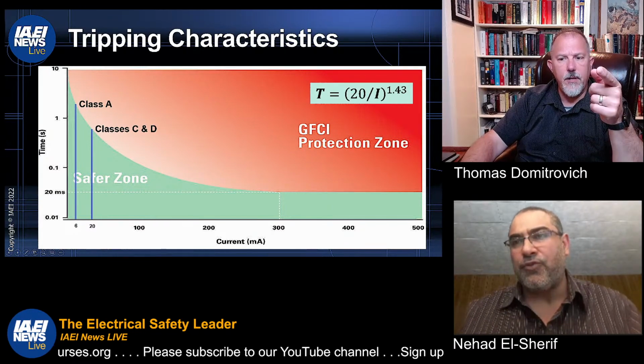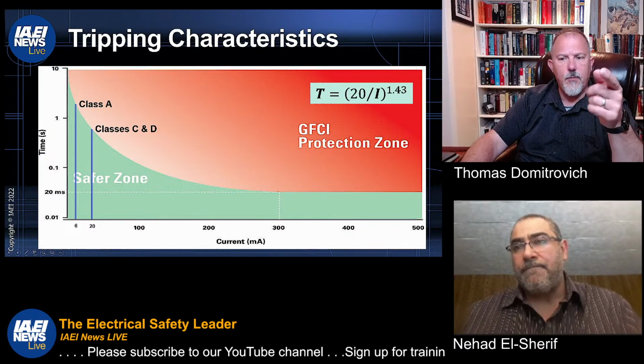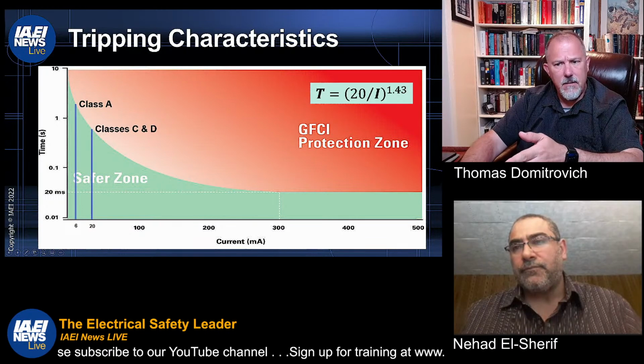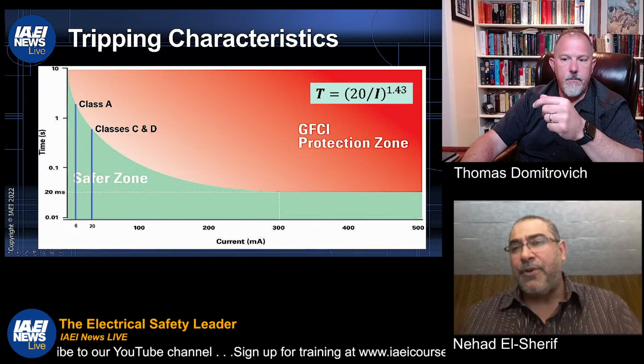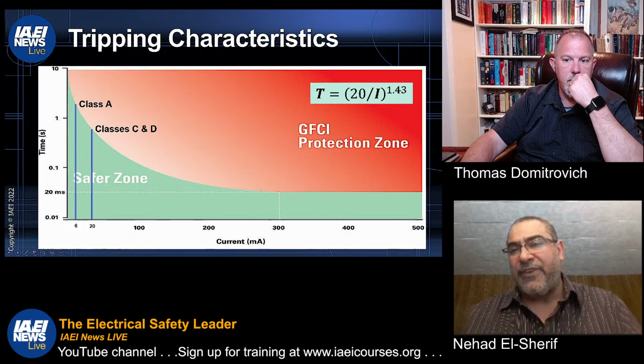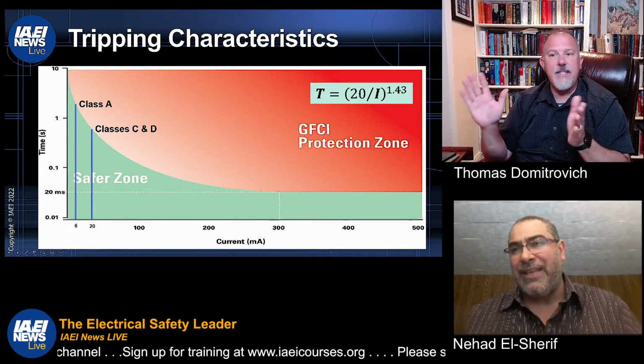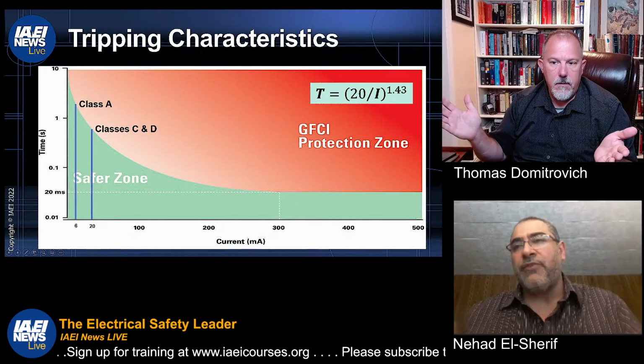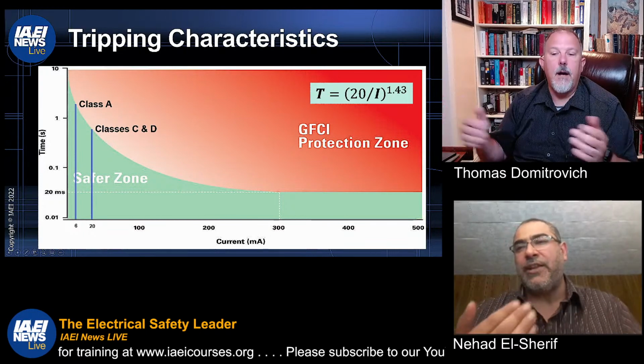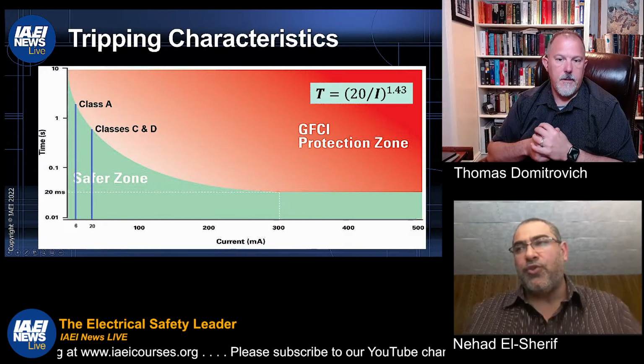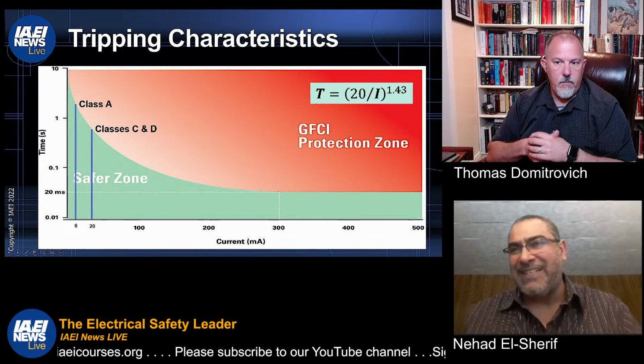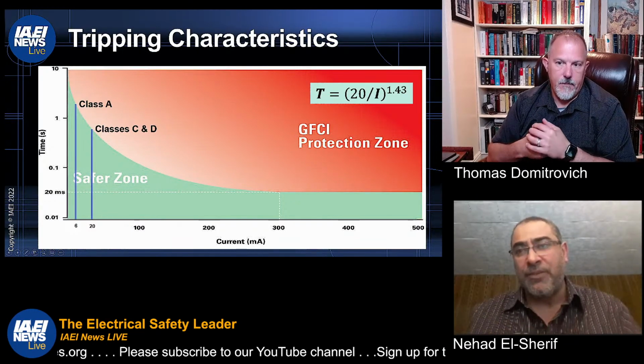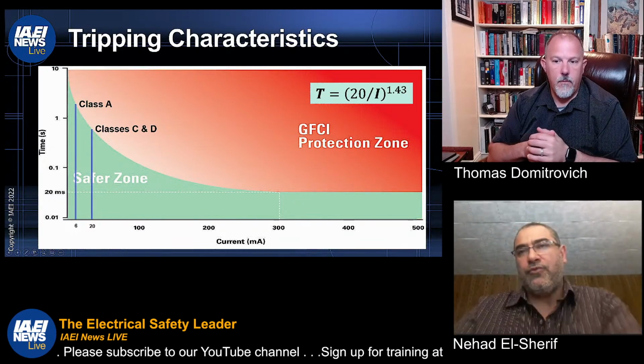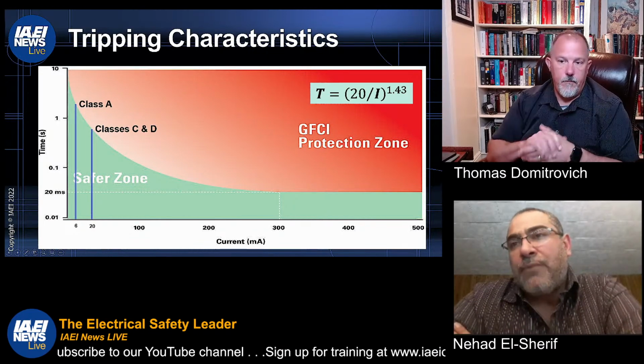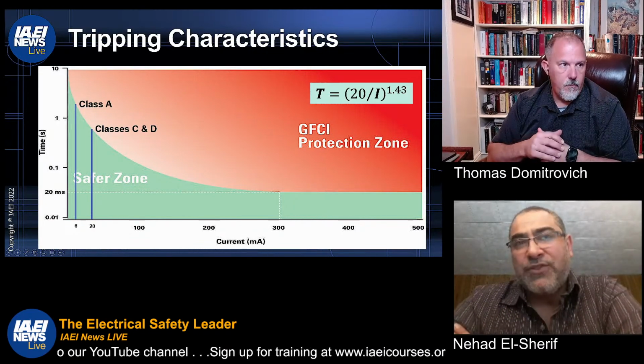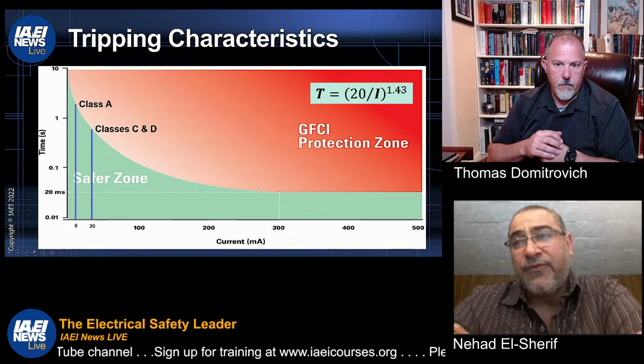What's that one on? You said that when you get to, is that a Class E? Class E. When you get to the 300 milliamp for Class E, you don't have the fixed time anymore. Okay, but Class Es don't exist. Right, and this is the reason it doesn't exist, because the new equation is much, much quicker. I think you're required to trip within 6 milliseconds or something, which makes it impossible for a mechanical device to do this. Gotcha. In the future, I'm sure there'll be technology that could meet this, but as we speak today, Class E does not exist for this reason.